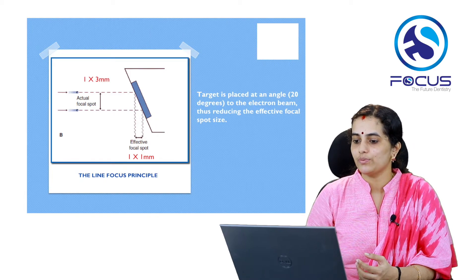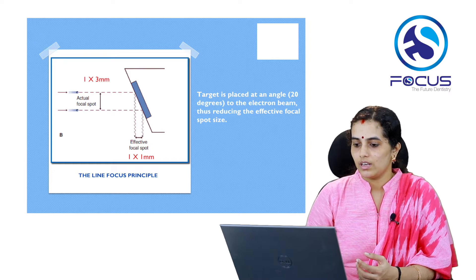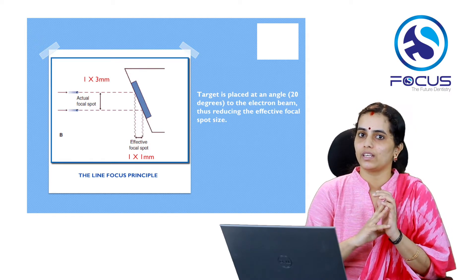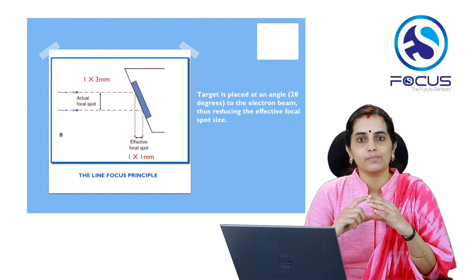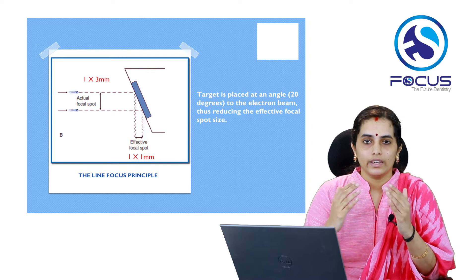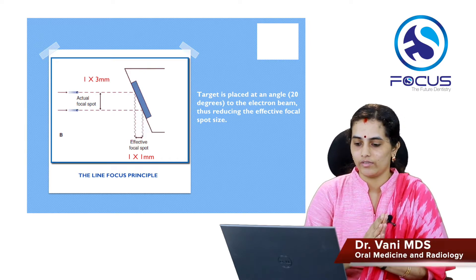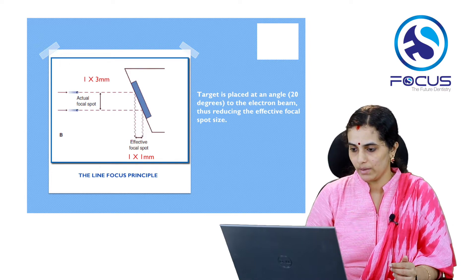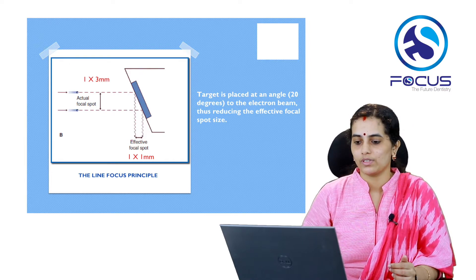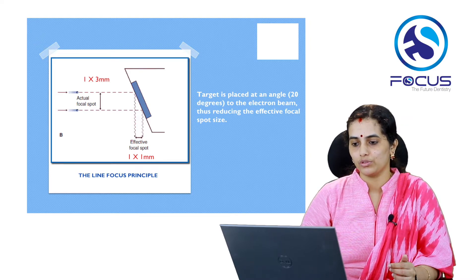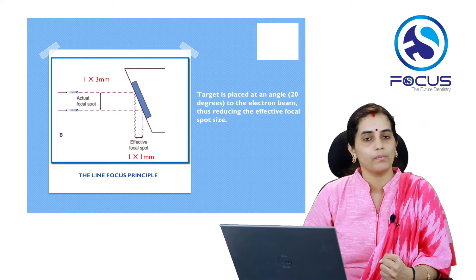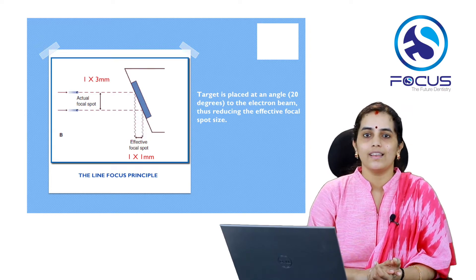Now let us look at the arrangement of the tungsten target. For good image sharpness, we need as small a focal spot size as possible. However, reducing the focal spot to bare minimum risks damage from heat generated. To overcome this, the target is placed at an angle of 20 degrees to the electron beam. This reduces the actual focal spot size of 1 by 3 mm to an effective focal spot size of 1 by 1 mm. This principle is called the line focus principle.